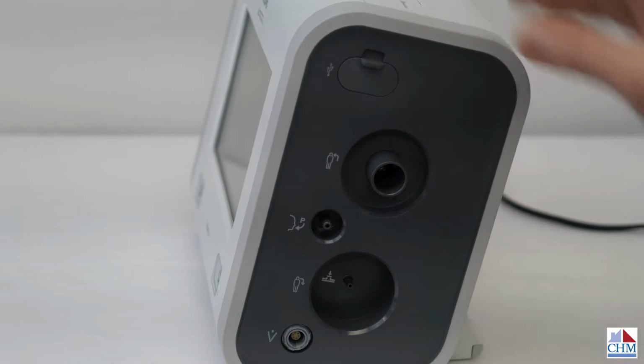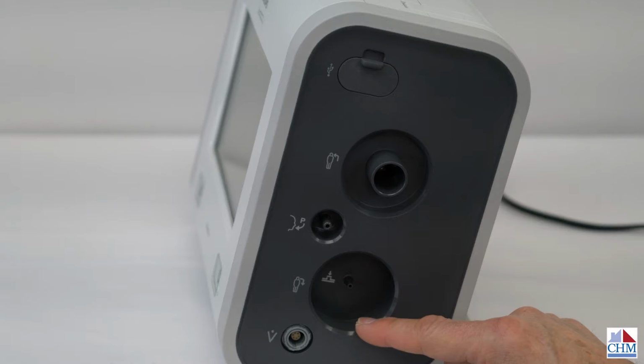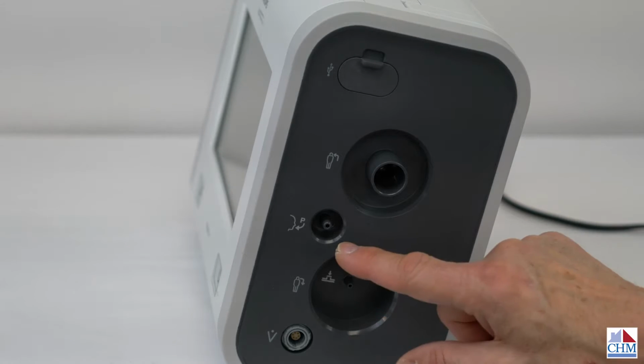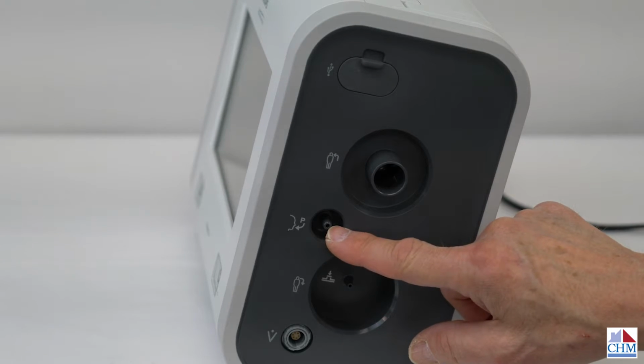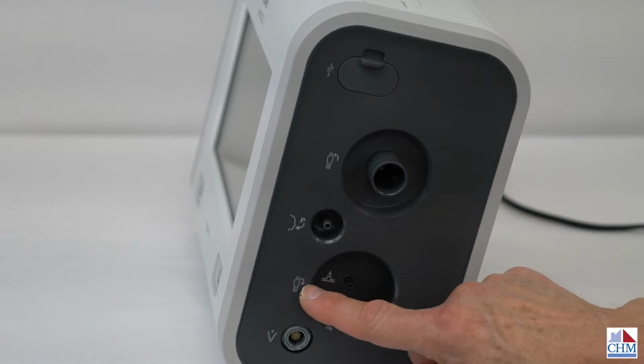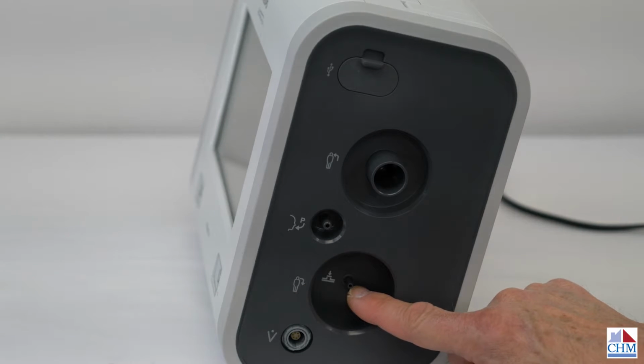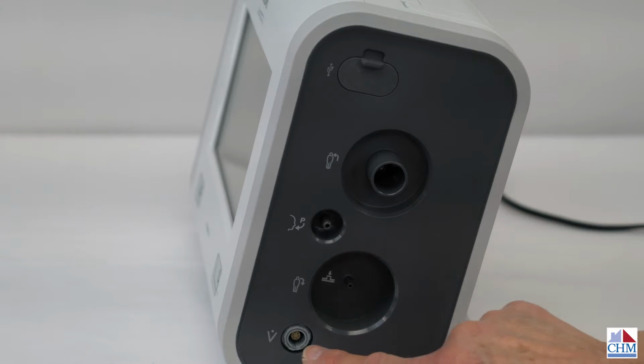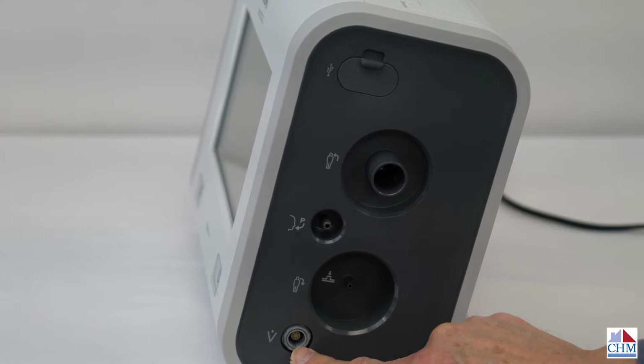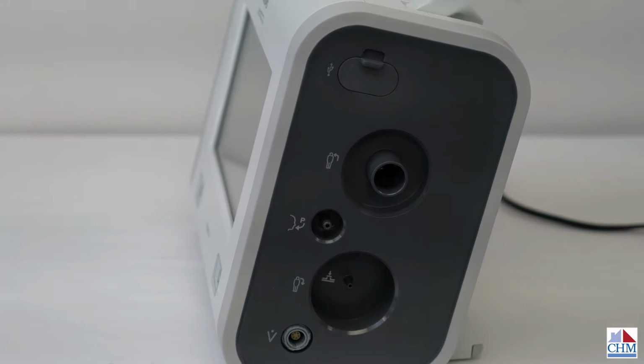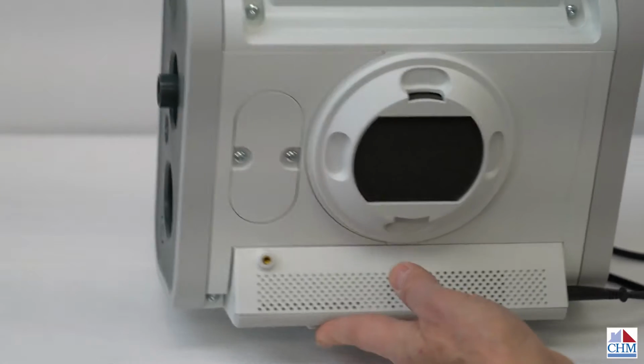And then we've got, depending on the type of circuit that we're going to use, if we're using an active circuit, this is where our pressure line would go. And with the active circuit, this is where our exhalation valve would be attached. And here we've got a connection for monitoring devices, CO2 and end-tidal CO2 and that type of thing. We'll go ahead and go around to the back of the machine.